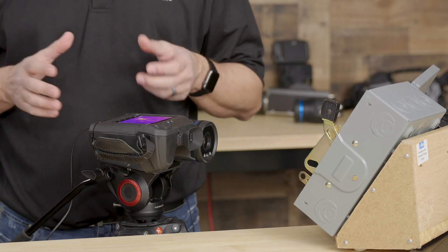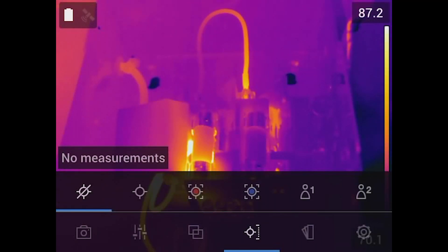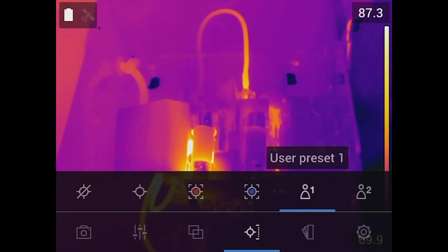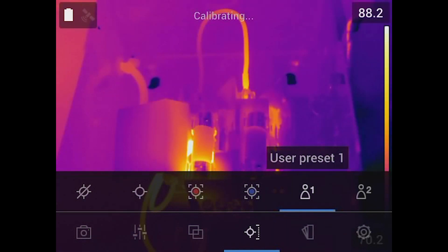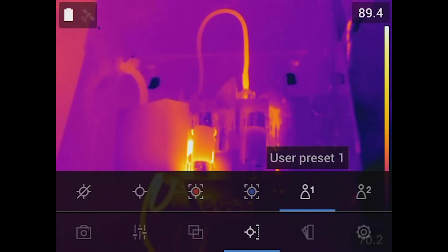Let's talk about more measurement features. Under measurement in the menu structure, we have a couple of actual presets — user preset number one and user preset number two. Instead of just adding one spot or box, you can add multiple spots or boxes and save all those functions as a preset. When you boot the camera back up, you can load your user preset — for example, a box showing maximum temperature plus a spot as a reference temperature to calculate a temperature differential, or delta T.